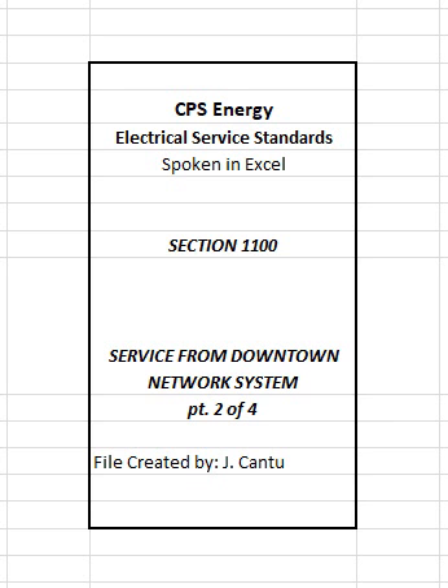4. Transformer vault or room ceilings shall have a 30-inch diameter personnel entrance where required for outside access by CPS Energy authorized personnel. The ceiling shall also accommodate concrete inserts as specified by the CPS Energy customer service representative for support of secondary bus.